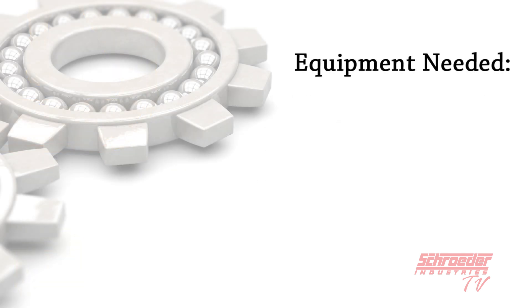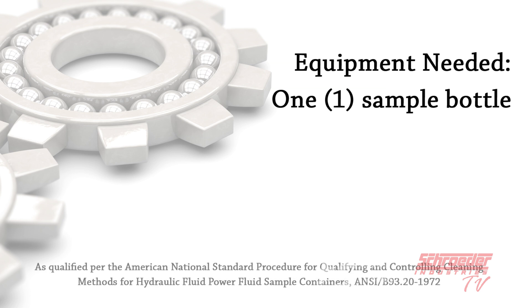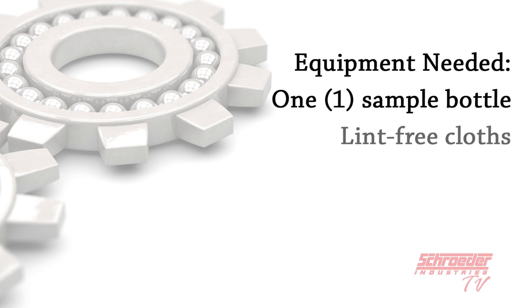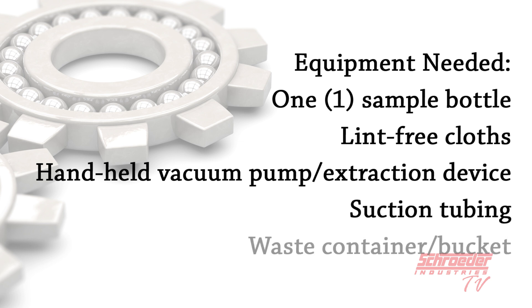Equipment required to perform the direct sample draw includes: one sample bottle cleaned to a level at least two decades lower than the expected sample, as qualified per the American National Standard Procedure for Qualifying and Controlling Cleaning Methods for Hydraulic Fluid Power Fluid Sample Containers, or ANSI B93.20 1972; lint-free cloths; handheld vacuum pump or acceptable extraction device; suction tubing; and a waste container or bucket.